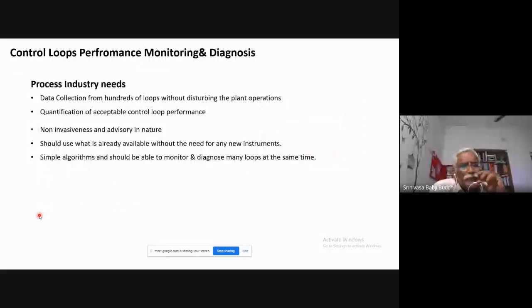So what is the industry primarily looking for? The needs are: we have hundreds of thousands of loops, so they need a system which will be able to collect the data from all these control loops without much problem, without disturbing the plant operations. Then the performance of the control loop should be quantified. Like you should be able to tell, okay, 20%, 30%, 40%. Simply saying good or bad is not sufficient for the plant engineer. So you need to quantify the performance of the control loops.